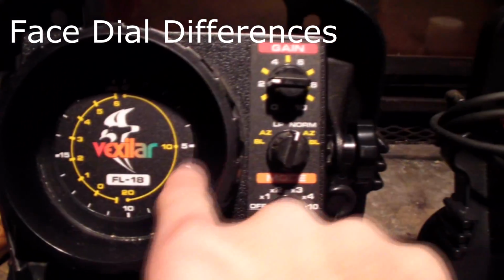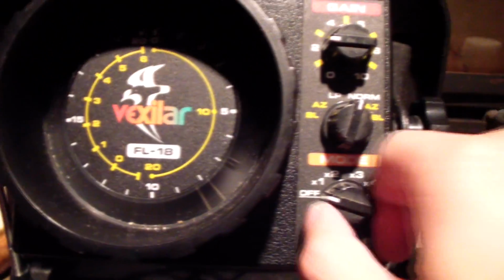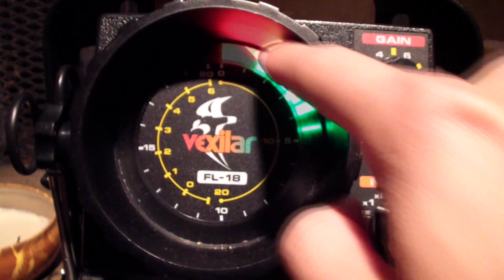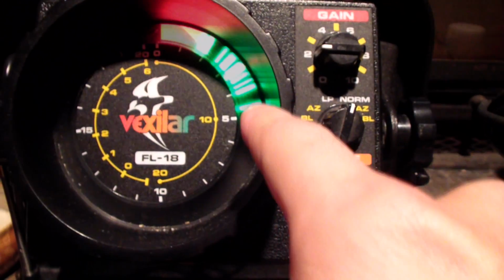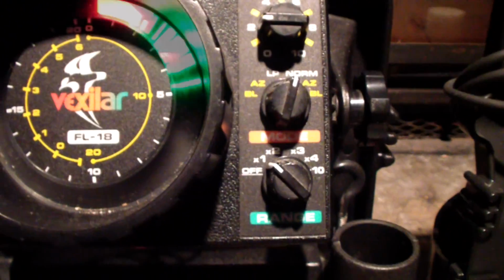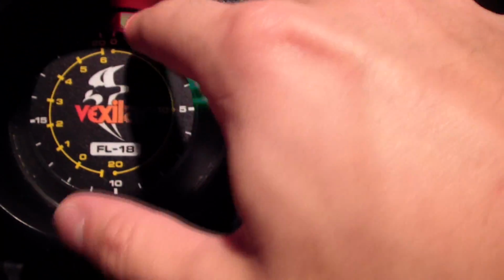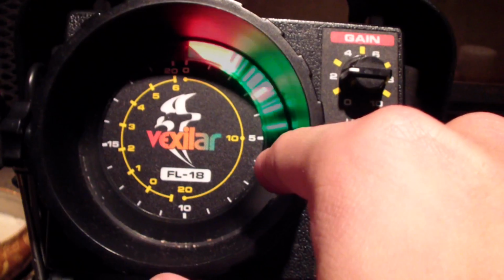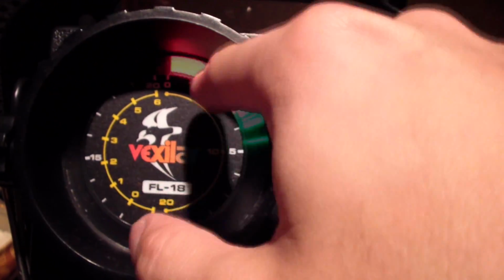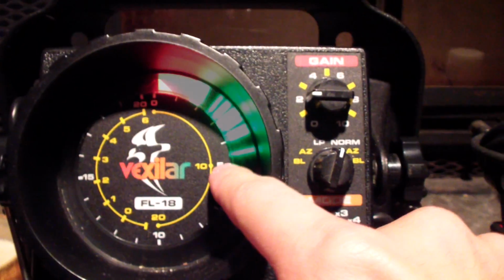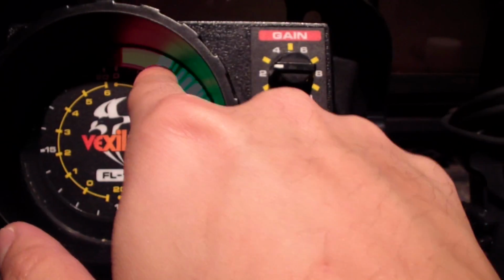Alright, let's talk about the actual face plate or face dial of the actual unit. The first thing you'll notice is the FL18 actually has the markers on here. So it kind of tells you there's less guesswork because you can visually confirm it. So let's see if we turn it on, put it on to normal. We're on 1X normal, and it's showing, alright, what do we got here? There's a lot of crap going on. And since we don't have water, it's real hard to differentiate what it is, but it's saying that, alright, 3 feet is what the transducer puck is reading. The stuff past it is junk. So that's how I can read this. It's around 3 feet. So you have the little markers, and if you're on 1X, it's the outer ring, and so forth and so on. So I'll turn this off.